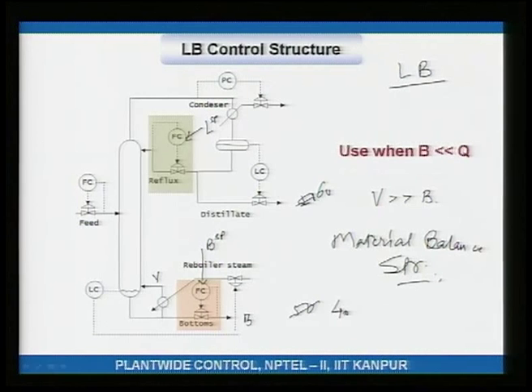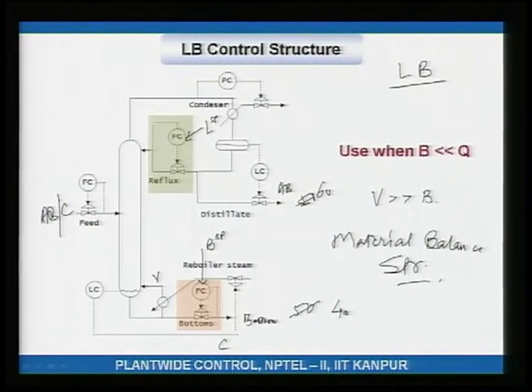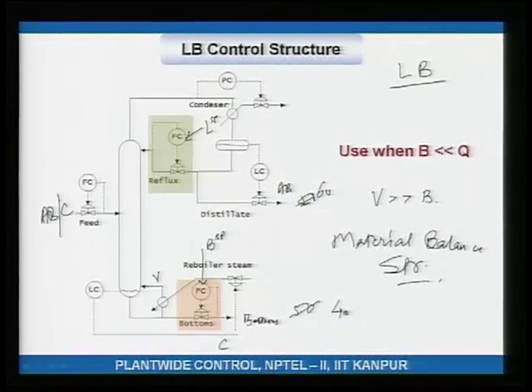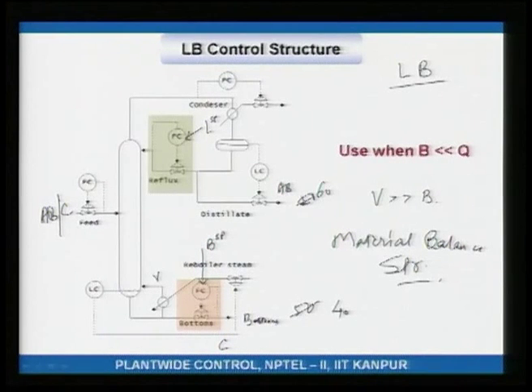You would use the LB structure when, for example, with components A, B, C, where C is very small compared to A and B — taking C down the bottoms and A, B up the top. Since the bottom stream would be very small compared to the boil-up, you must control the bottom level using reboiler duty rather than the bottoms stream.